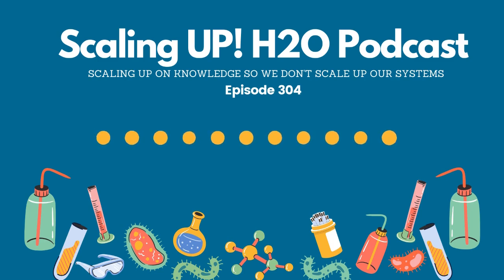So a lot of times I will weigh a corrosion coupon, and let's say it will come back as good. And that would be a 3.1 mils per year. Well, now let's say that corrosion coupon is pitted. Well, even though it weighed to where it said it was good, pitting is never good. Pitting is never acceptable. So when you look at the rates on what is acceptable and what is not, you have to remember that pitting is never acceptable.